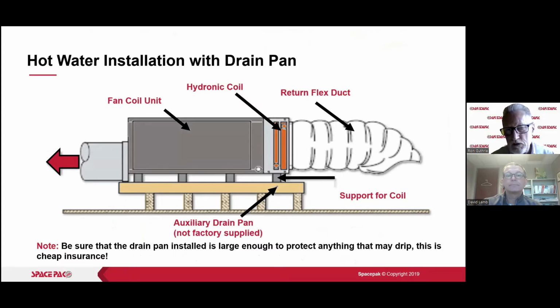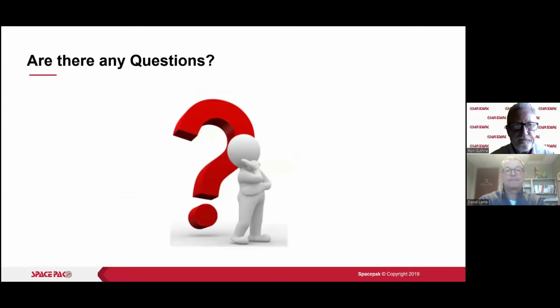But the thing is, when you do put a hydronic coil on the end of our unit, our drain pan does not cover that hydronic coil. So it doesn't protect from leakage from the hydronic coil or fittings or whatever. That's one thing. At that point, you'll be either making one or using a larger prefabricated drain pan.